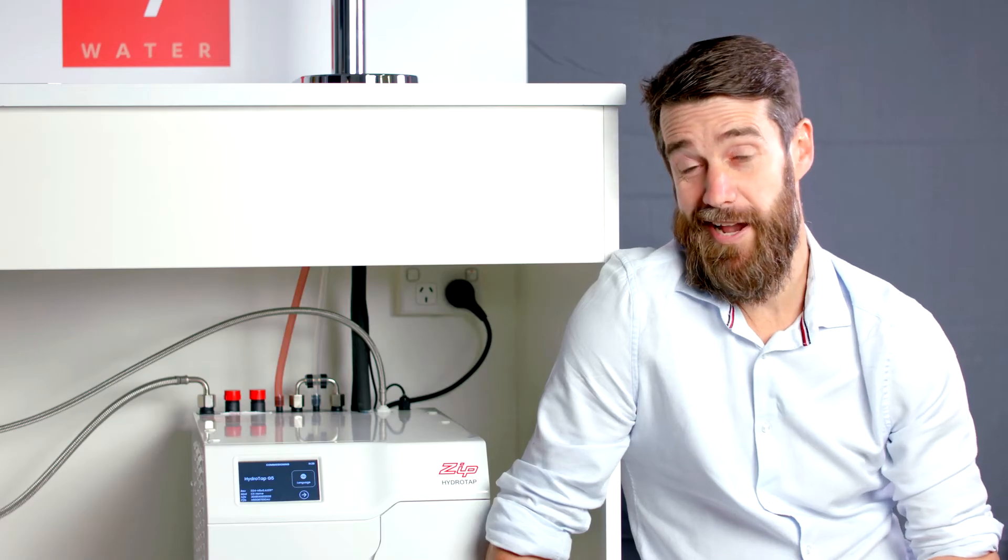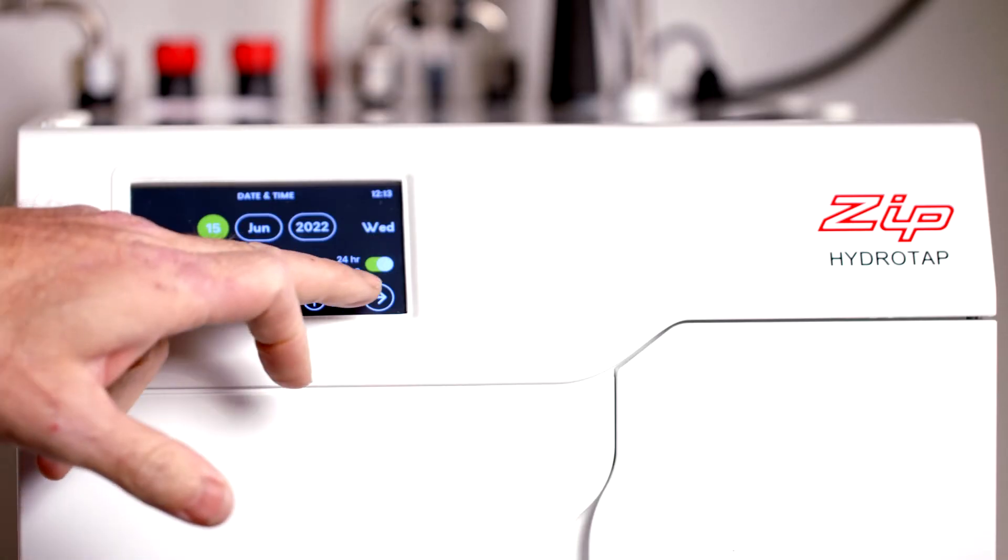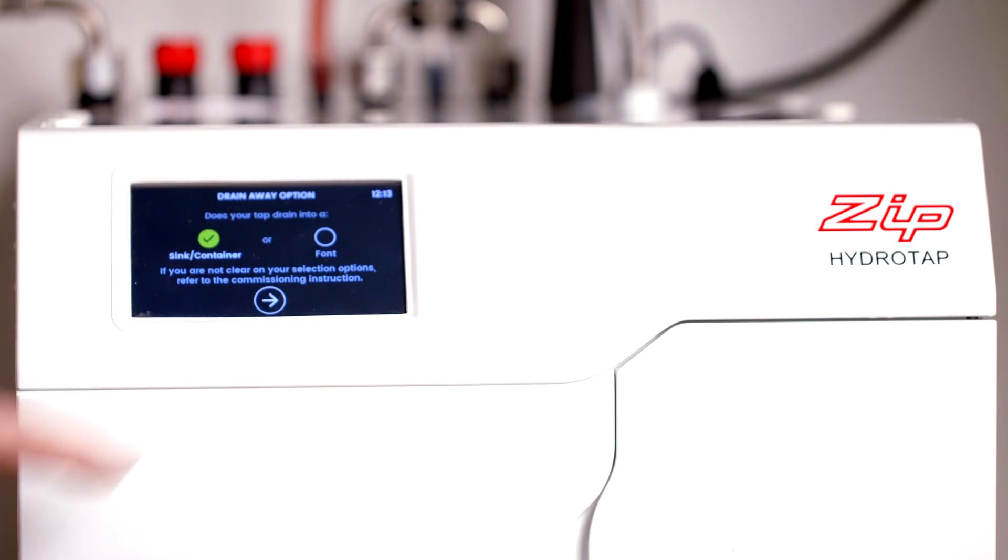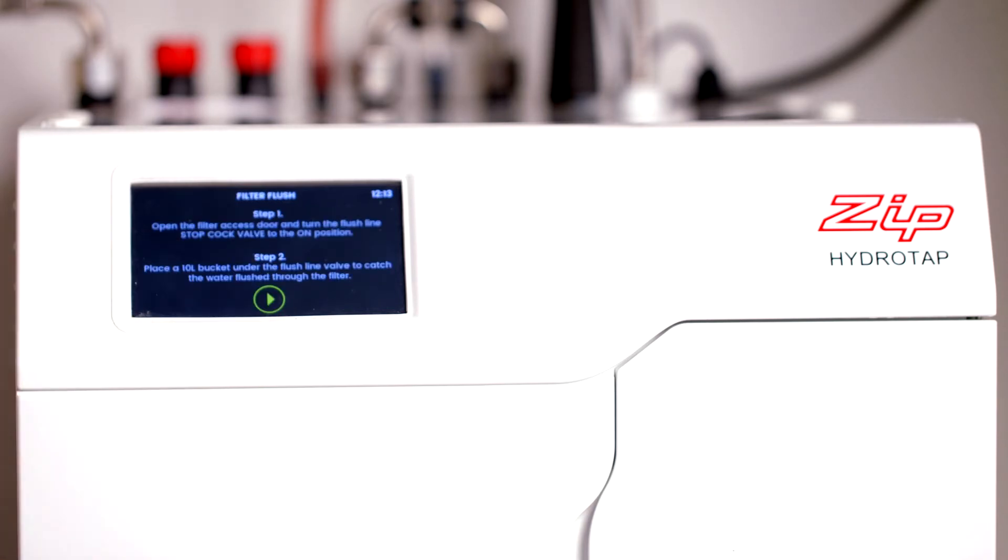The next screen asks you to select the drain away option. This simply means if your tap or faucet is installed to dispense into a sink or the specially designed Zip font. If you select sink container, the flushing process from the tap will be automatic. If you select font, you'll need to use the tap or faucet to dispense water during the commissioning process.